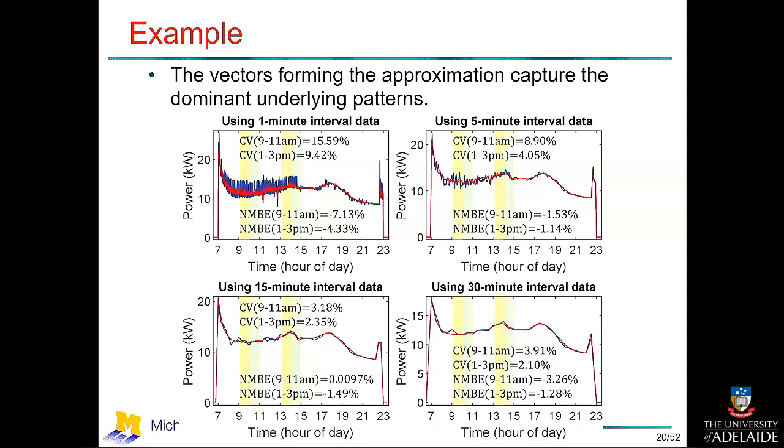understand the dynamics of the HVAC system. The motivation behind all this was some testing that we originally did at Los Alamos National Lab, which showed that when you think of a building as a battery, energy in versus energy out, it's about 50% efficient. So it begged the question, why is that the case? We're really exploring using measurements and then trying to build some models to explore the physics going on there, and how that's impacted by different types of buildings. So we have these 10 buildings telemetered.